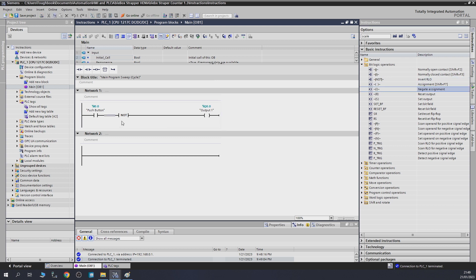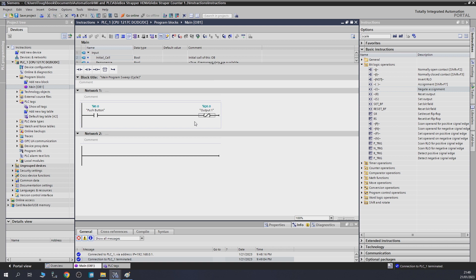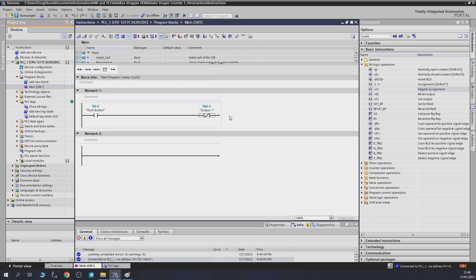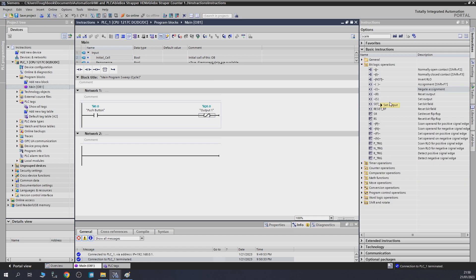That is NOT. Next let's check out what negative assignment means. We're going to remove the NOT and put in a negative assignment coil. What negative assignment does is invert the specific coil. Let's compile and load it. As you can see, the coil is receiving a signal ON but the coil is actually OFF. If I turn the button OFF, the coil turns ON. So it's pretty much like NOT but targeted to a specific coil — really useful for signal swapping.